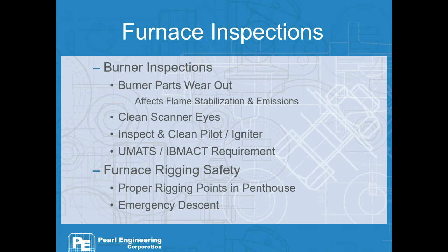Your startup time can be decreased coming out of that outage if you take the extra effort and make sure that your igniters and burners are ready to light back off. They don't get used that often, usually just coming out of an outage. And now, like I said, it's a UMATS and IBMAC requirement that at least every few years, depending on if you're UMATS or IBMAC and your size, the burners do get inspected.